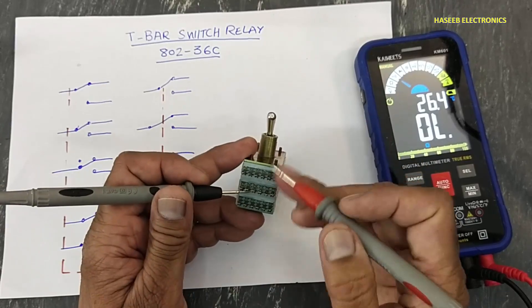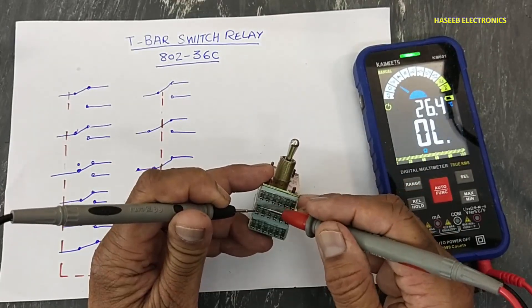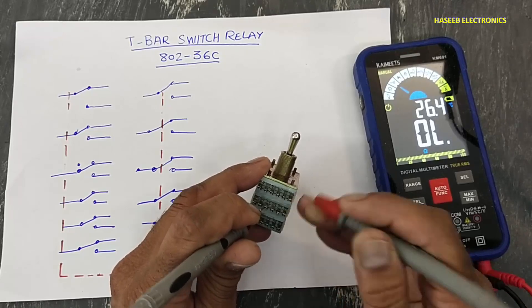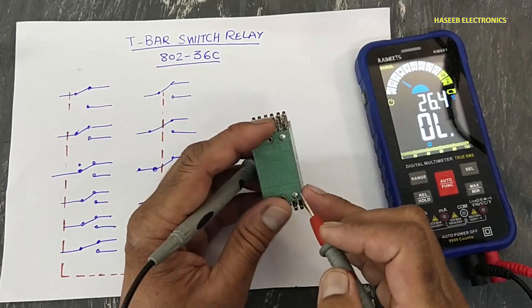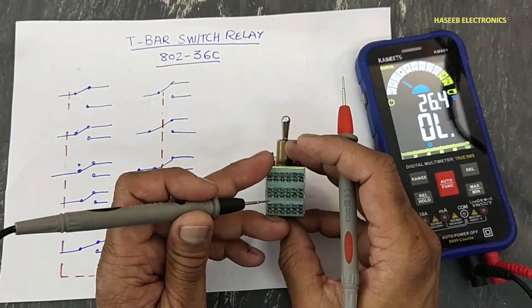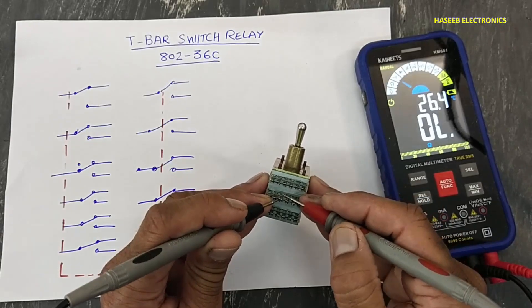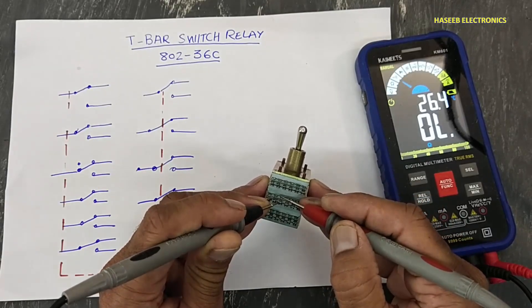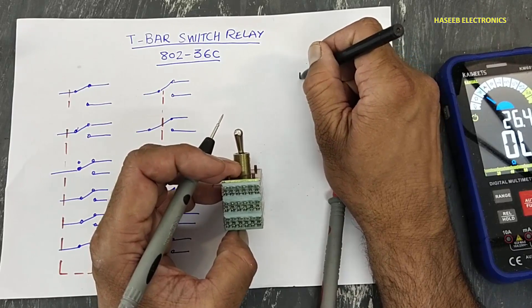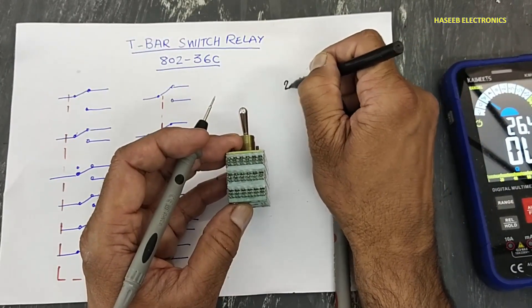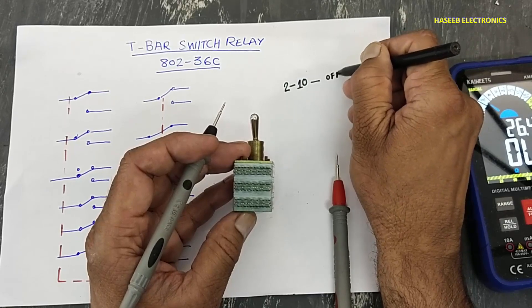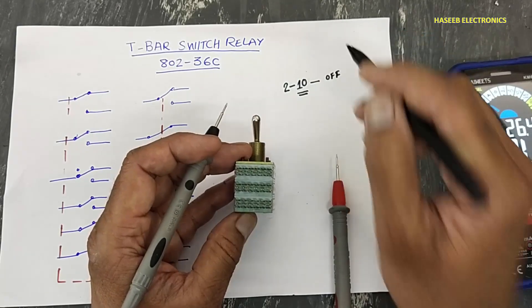I have a problem in this second stage. It is making connection here on this one, but contact number 3 is not making connection here. Counting the points: 1, 2, 3, 4, 5, 6, 7, 8, 9, 10 — in the second stage, point number 10 is not making connection in the OFF position. I will write it here: stage number two, contact number 10 is not connected in OFF position. This is our first problem.